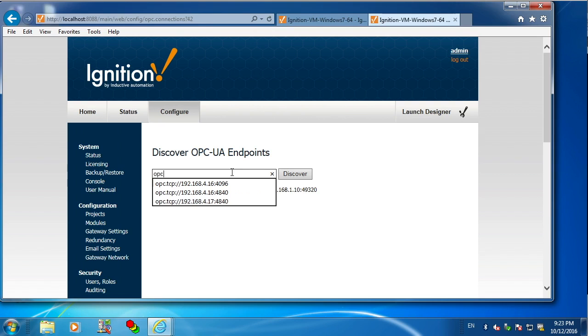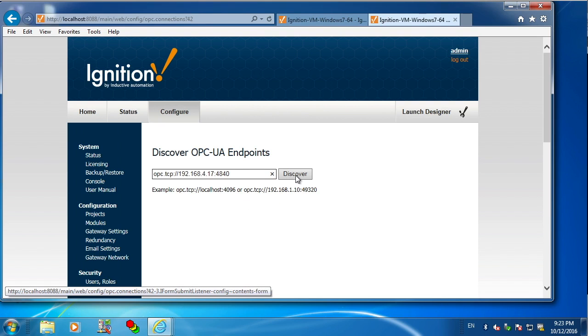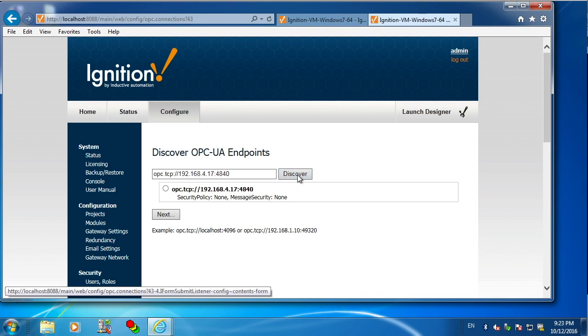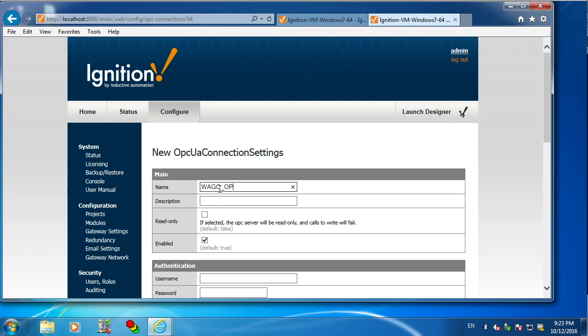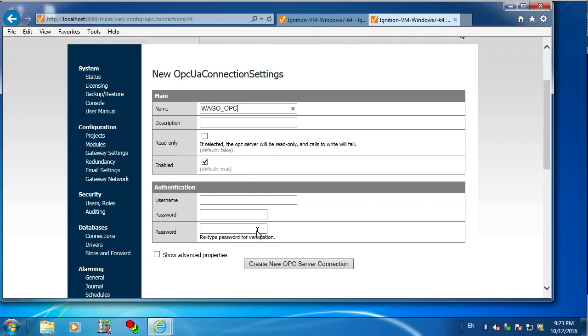And I just type in the IP address of my PLC followed by the port, which is 4840. Click next. I just have to give a name to this. I'm going to call it WAGO OPC. And then we can click create new OPC connection.